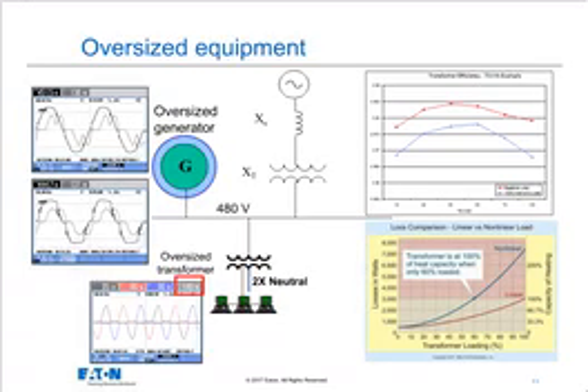Now, as far as what people used to do with harmonics, and still do today in some cases, is that they oversize the equipment. It's again a bit of a Band-Aid approach, but it's putting on some additional capacity so that you can withstand the amount of heating or misoperation that may occur. If you look at the top left, oversizing the generator. If you took a 1,000 kW generator and a 1,000 kVA transformer and you compare their impedances, it'd be about a 3-to-1. So if I take that 1,000 kW generator and make it a 2,000, now my impedance is half on the 1,000 kVA base. So instead of going from 6% impedance to 18%, I'm going from 6% to 9%. Not horrible, but still not as good as it would be on the utility source.